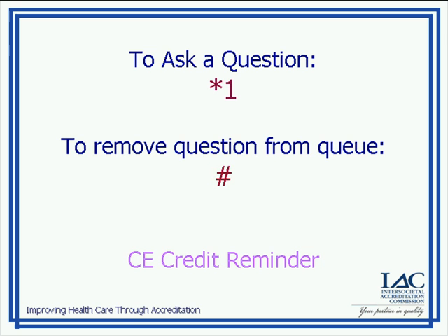Yes, I do have a question on the center of rotation. It says it must be performed to ensure mechanical and electrical alignment of the center of field of view. But is that required for all collimators we use, or currently we only do COR on LEHR? And that's fine. We're not requiring that you show us on all of them. If it's your most frequent, the only one you're going to have to submit to us. At the time of site visit, we're probably going to look and see that you are doing it. If you're frequently doing gallium studies and you're doing gallium SPECT and you're doing it frequently, then you should be doing CORs because mechanical and electronic heads can change.